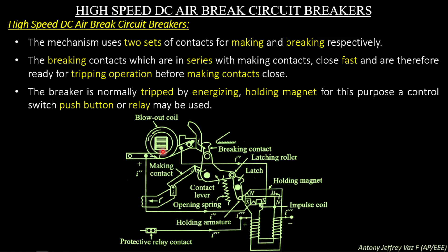In case of a short circuit fault, the relay will trip the holding armature, and at once the latch will be opened. At once the breaking contact will be separated and the DC circuit breaker will interrupt the short circuit fault. At once the arc will be produced, and this arc will be blown out through the blowout coil which is present within the DC circuit breaker.